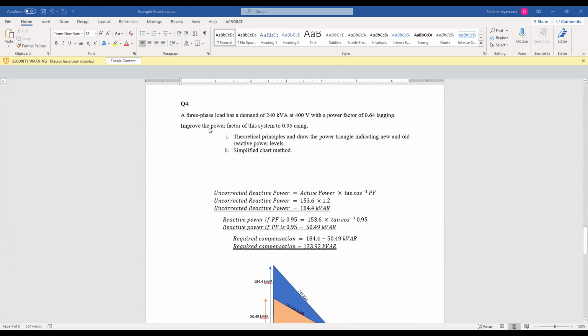Okay. Now we are coming to power factor correction. So power factor correction, I think you should listen to the lecture. I uploaded a recorded one. So power factor correction is actually a very easy thing to do. So what you have to do is you have to reduce your reactive power amount. So usually reactive power component is caused by inductors or inductive elements in your system. So what we do is we add capacitors to compensate for that inductive element, so it will get reduced and your power factor will be corrected. So this is actually, I think, first year electrical systems design knowledge.